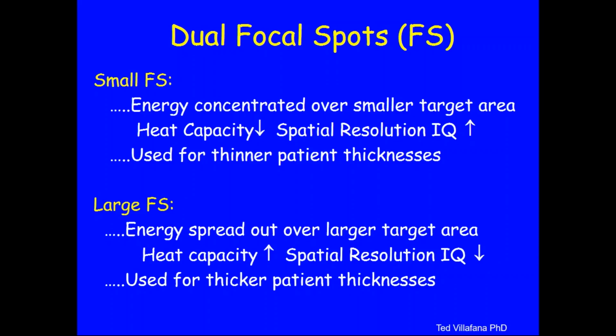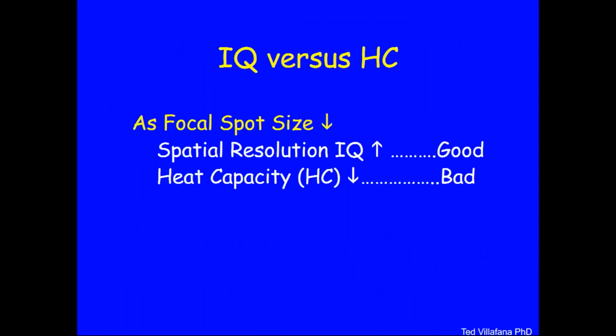It won't expose for you, and you got to then go searching for a combination of techniques, or go to a larger focal spot, or a combination of techniques where the machine will allow the exposure for you. So you do have that built-in control, and thank goodness for it, because many times you would take the wrong settings and blow up a tube.